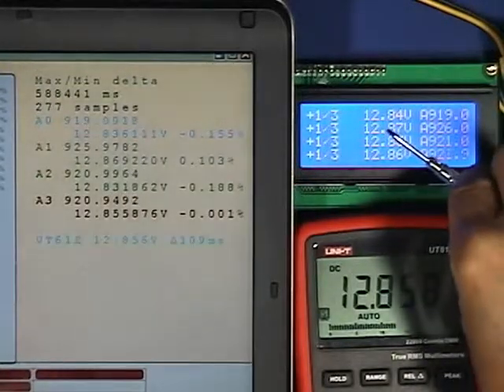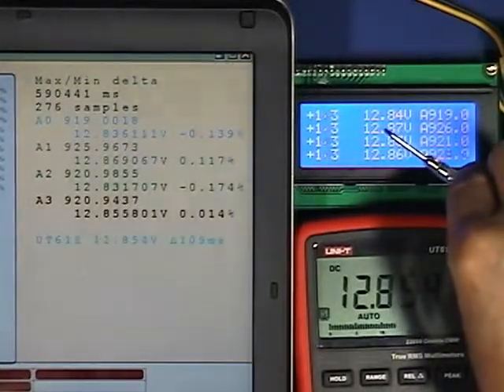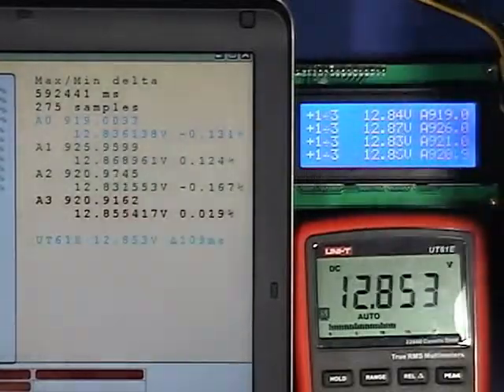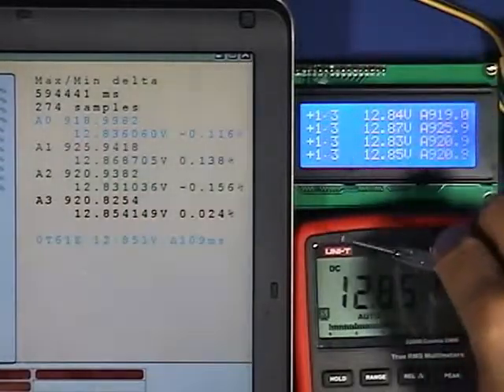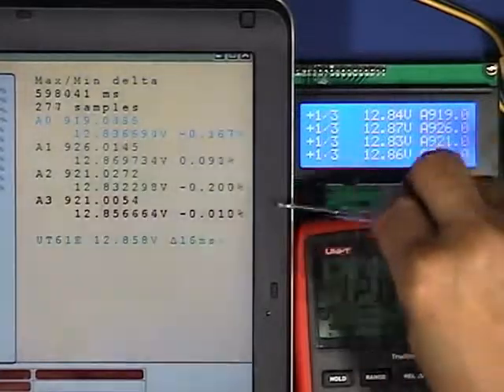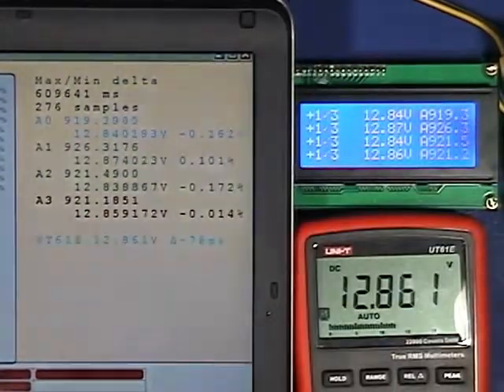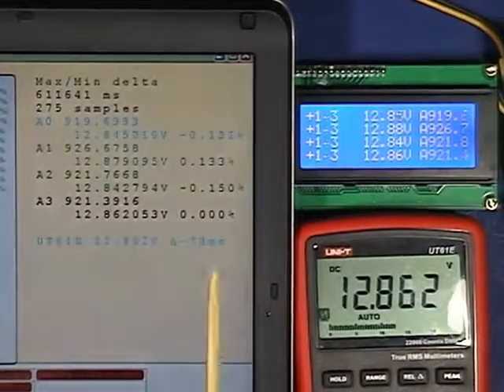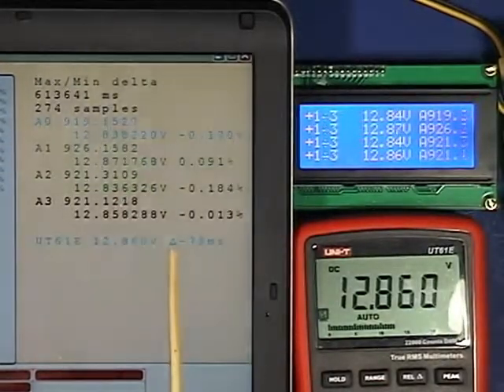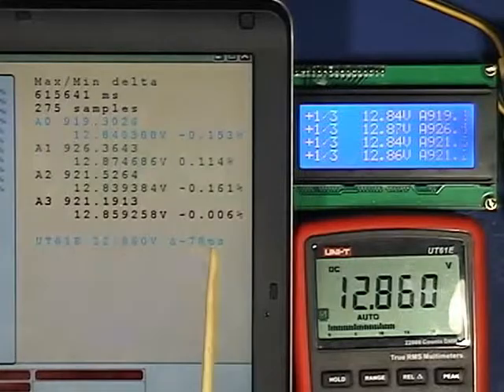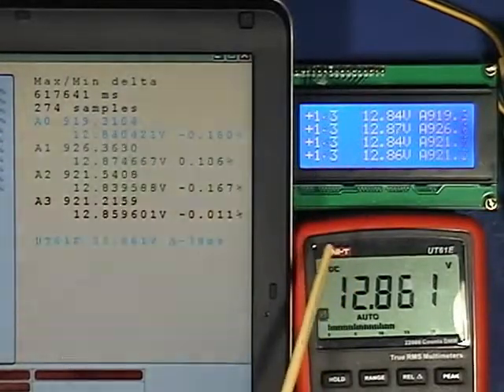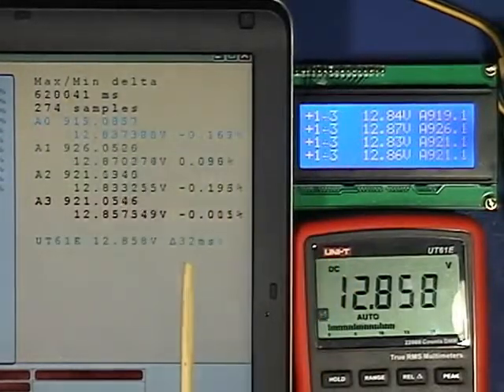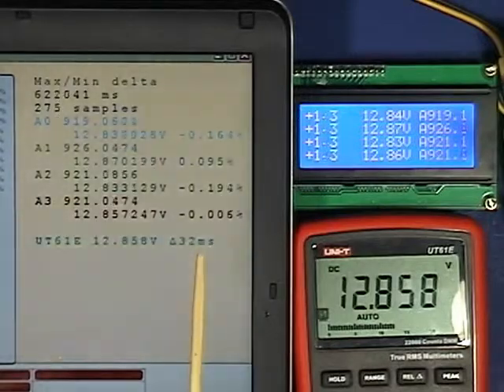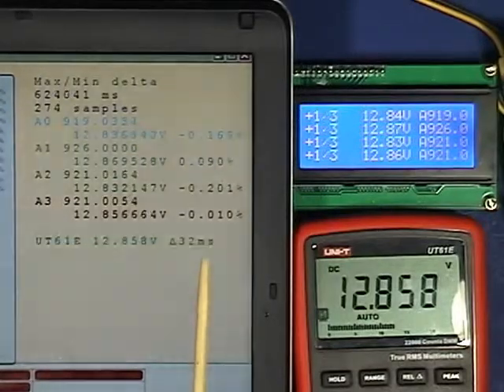This guy is reporting at a quarter second. When the voltage is changed very quickly, in that quarter second difference, the voltage already changed significantly. We register a very high percent error. That's why, to do proper calibration, I display the time difference between the two records. I am reading it about 200 milliseconds behind.